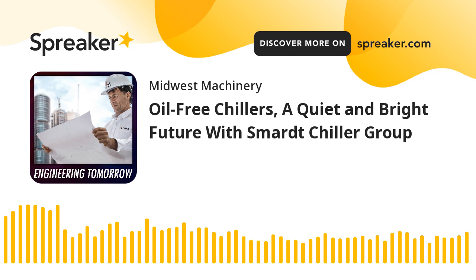Out in the distant future, our technology has capacitors, just like all magnetic bearings do, and those capacitors would need to be replaced. Currently we measure that at about a 10-year mark. However, not to go against the O&M manual, but right now we do have some machines operating that are older than 10 years and haven't had those capacitors replaced. So it would just be smart, when you get close, to make sure you have an extra set on hand.